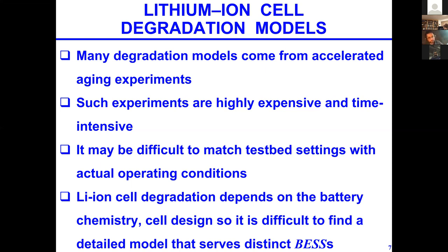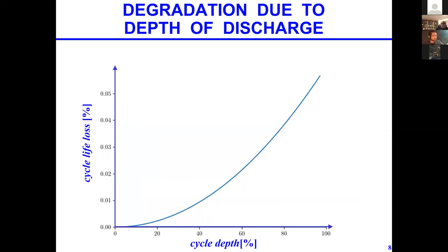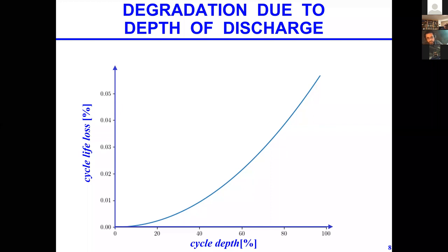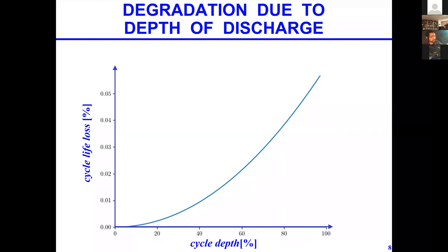That's the approach we've been using here. Our main concern is with the depth of discharge. Many batteries have a specified number of cycles they'll be able to perform during their life. If you do a cycle at 80% depth, you lose around 0.03% of that specified number of cycles. This is a curve for a certain type of lithium-ion battery.